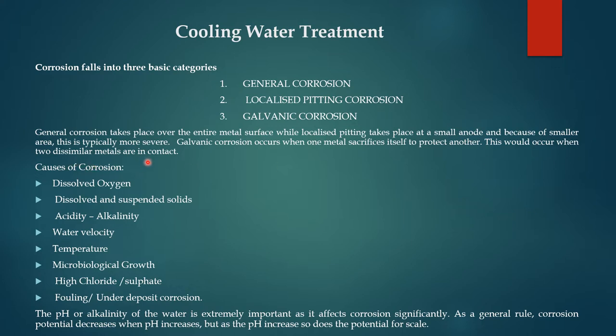Galvanic corrosion occurs when one metal sacrifices itself to protect another; it occurs when two dissimilar metals are in contact. The main causes of corrosion are: dissolved oxygen, dissolved and suspended solids, acidity or alkalinity in water, water velocity, temperature, microbiological growth, high chloride or sulfate content, and fouling under-deposit corrosion.